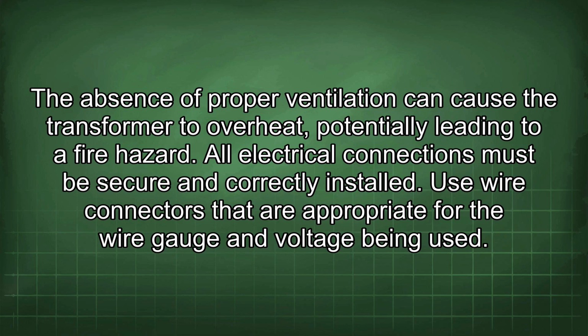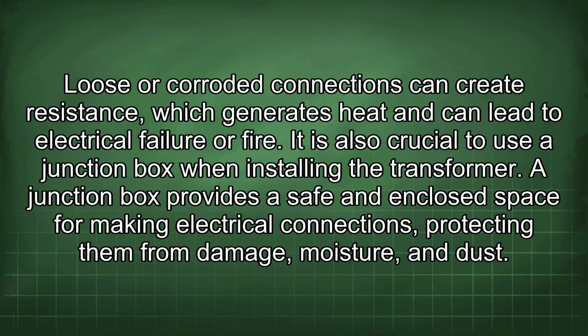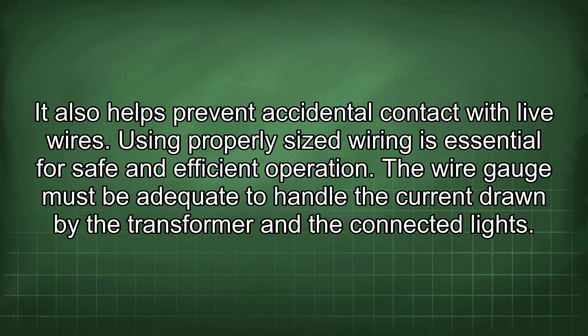All electrical connections must be secure and correctly installed. Use wire connectors that are appropriate for the wire gauge and voltage being used. Loose or corroded connections can create resistance, which generates heat and can lead to electrical failure or fire. It is also crucial to use a junction box when installing the transformer. A junction box provides a safe and enclosed space for making electrical connections, protecting them from damage, moisture, and dust. It also helps prevent accidental contact with live wires.